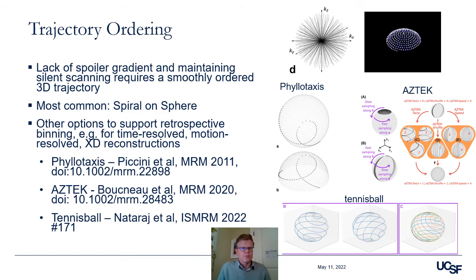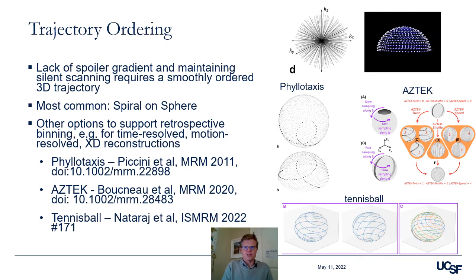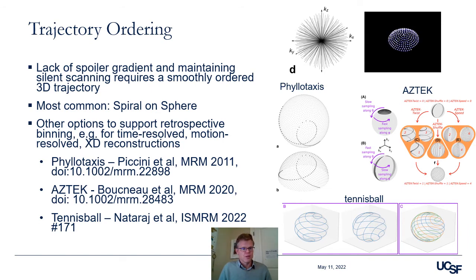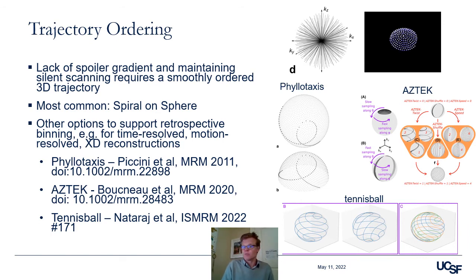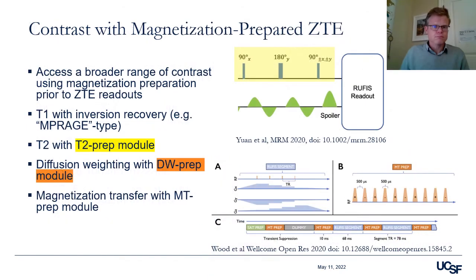For both maintaining the lack of a spoiler gradient and enabling silent scanning, you want to use a smoothly ordered or smoothly varying 3D trajectory. The spiral-on-a-sphere type 3D radial trajectory is the most common, but there are other useful options important for retrospective binning in time-resolved or motion-resolved XD reconstructions — including the phyllotaxis trajectory, the Aztec trajectory, and the tennis ball trajectory presented at this meeting.